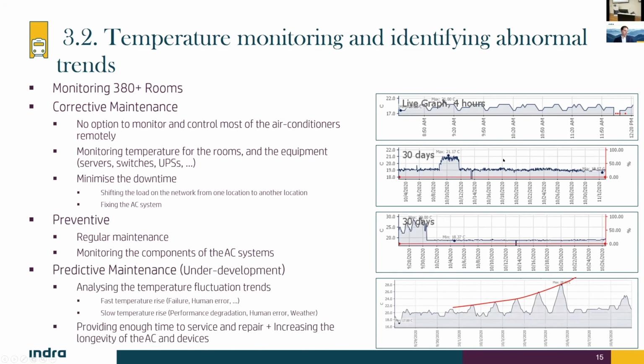Now the interesting part: predictive maintenance. We talked about corrective maintenance, where we fix an issue after it happens. We do preventive maintenance, which means you don't know if it will happen, but you're expecting it in the next, let's say, 6 months, so you do regular maintenance to decrease the likelihood of that problem. But predictive maintenance is another layer on top. It means I'm going to monitor the status of the system, collect some data, and from that data create a model or do some simple regression to understand the trend.